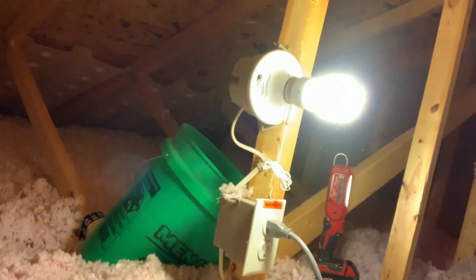We went from the RN2 EC cranked up to 10 pulling 42 watts, and dialed it down to 22 watts, which cuts the noise a little bit. But most importantly, it cuts the airflow so we're not pulling so much conditioned air from the basement. That's it for the attic — I'll put the cover on and head down to the basement to wrap up. I'm Jesse with American Radon. Thanks so much for watching.